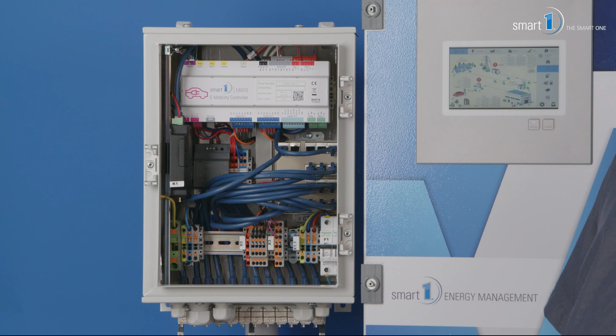And the next step that needs to be done is we need to do the configuration of the system. And I want to show you this. So the configuration is designed to be very simple, very fast. We will do that on the system right away. So I'm connected to my EASY2 system that is now running and live, and here I do the configuration. For example, I can set up the meter on the grid connection point. For example, if I have a Janitza meter, I would just select it here, enter the IP address of my Janitza meter, activate it, and then the setup of the grid connection point is done. You have a charging regulator, which is the CPS regulator, where you can set your limits.